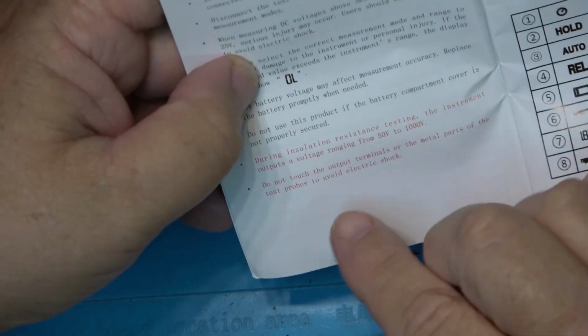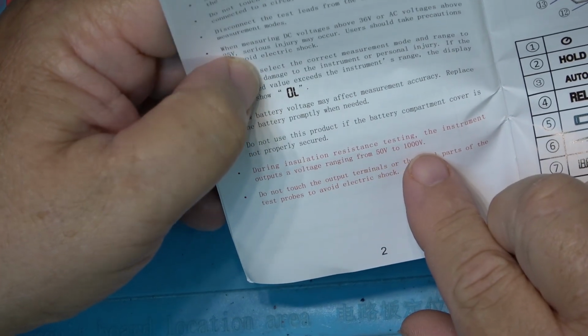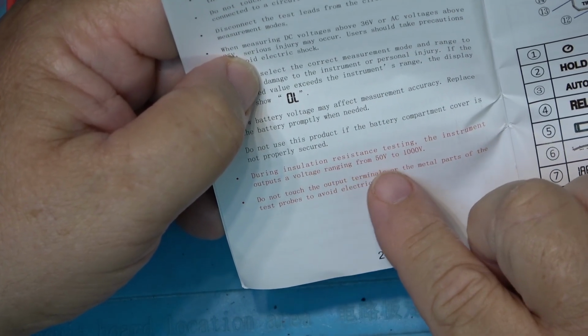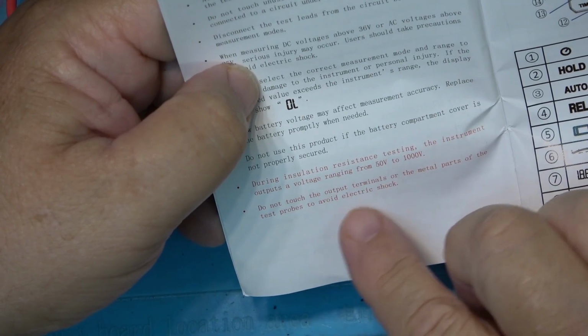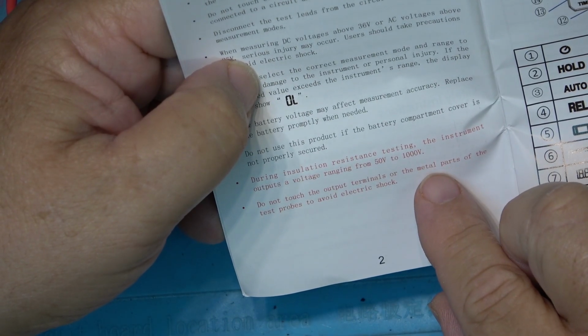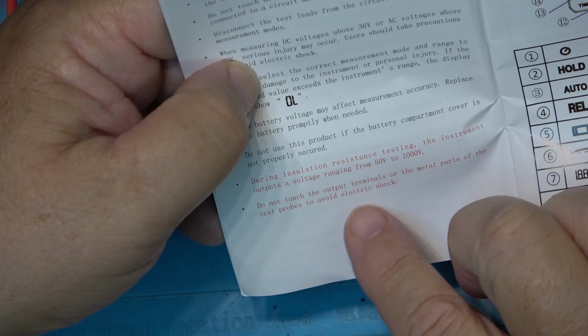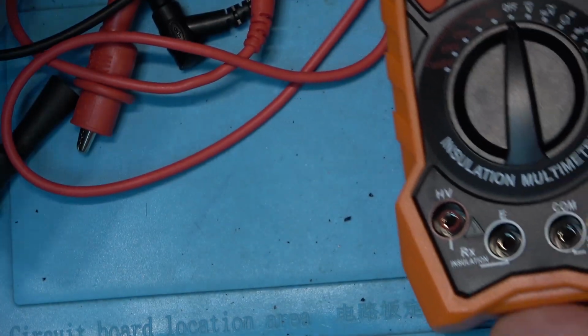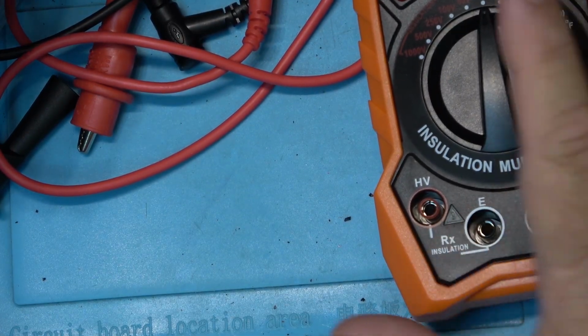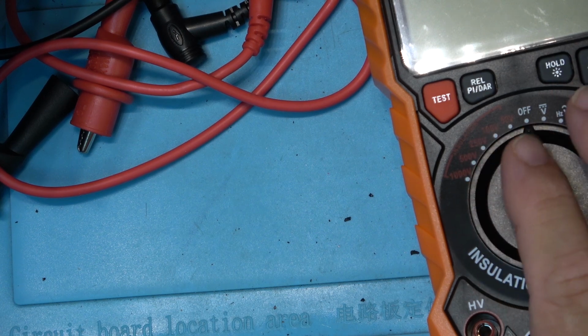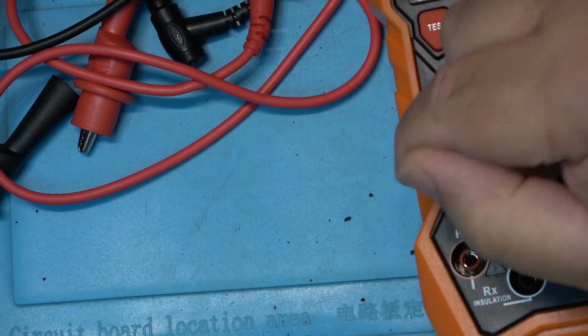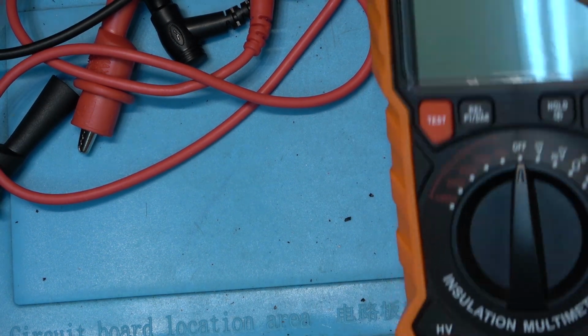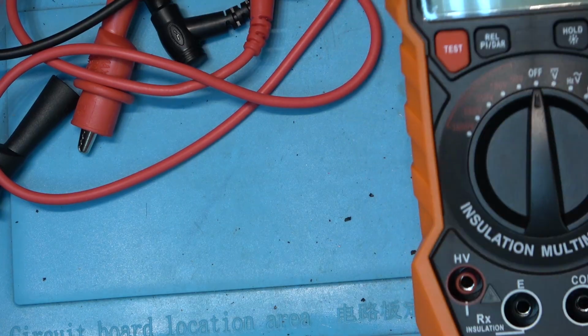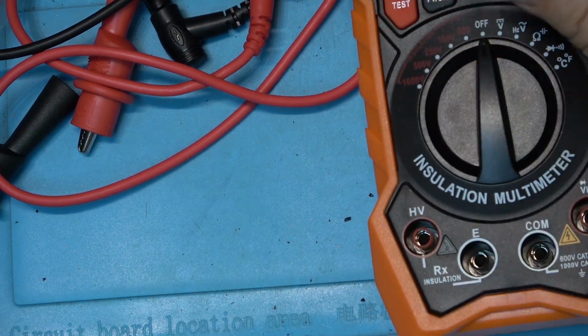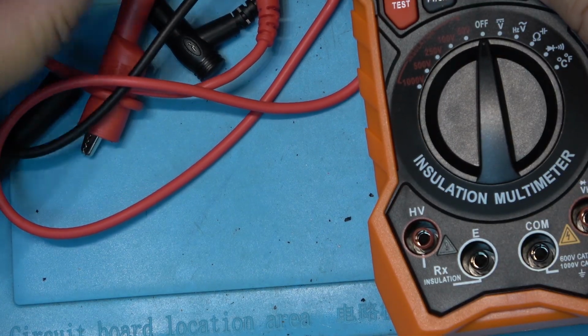Here it says, during insulation resistance testing, the instrument outputs a voltage ranging from 50 to 1,000 volts. Do not touch the output terminals or the metal parts of the test probes to avoid electric shock. So this thing actually will generate high voltage, and you can set it to what you want to test for breakdown, and it will generate a high voltage out here. So we'll test this. I'll see if we can generate 500 volts. We'll measure it with my other meter and just see what we can get out of here.